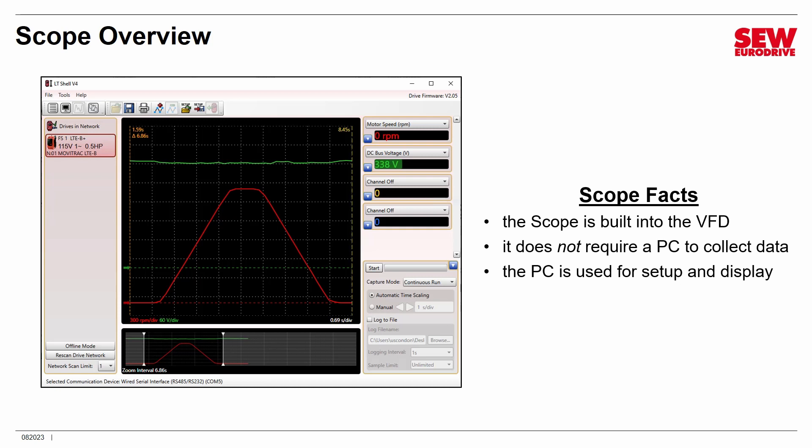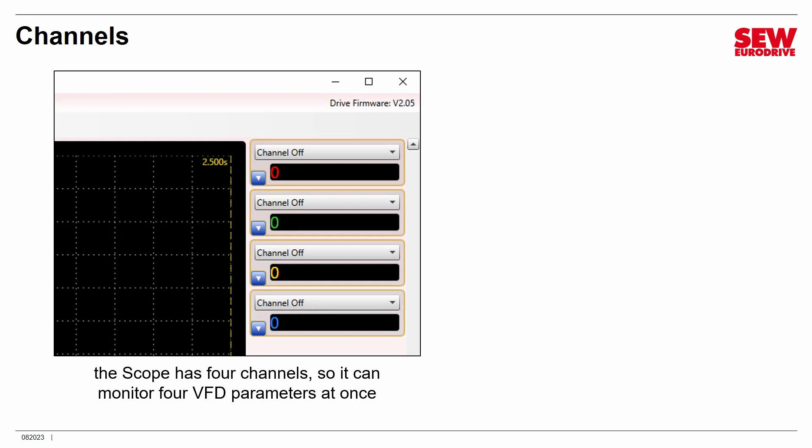This is extremely helpful for diagnostics and fault tracing when the fault may only occur very rarely. The scope is a four-channel scope — it can monitor four VFD parameters at once. The channels are currently all turned off. You do not have to use all four, but you can use up to four at a time if you wish. Notice each one has a unique color that will match its trace on the scope display.